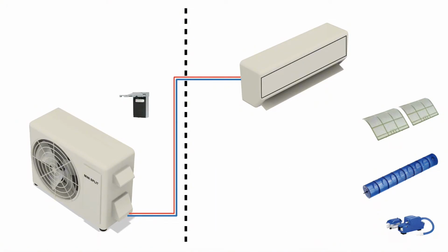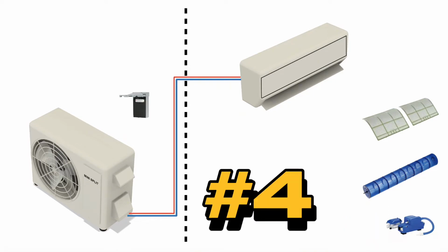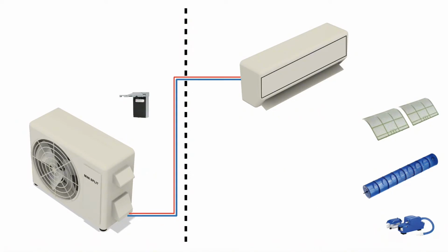Item number 3 is to inspect and clean your condensate drain line. If you have a little condensate pump like you see here, make sure you clean it. Maintenance task number 4 would be to clean the evaporator coil inside the head unit and the condenser coil outside at the outdoor unit. And finally, maintenance task number 5 would be to check the discharge air temperature coming out of the head unit when it's running, of course, to see if it's blowing out cold air.